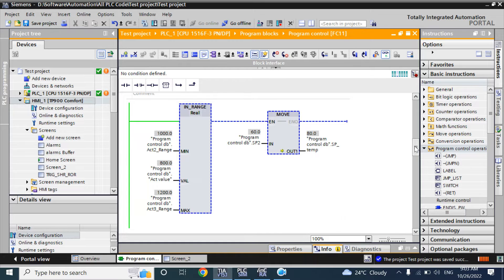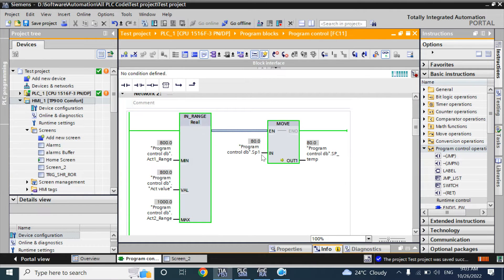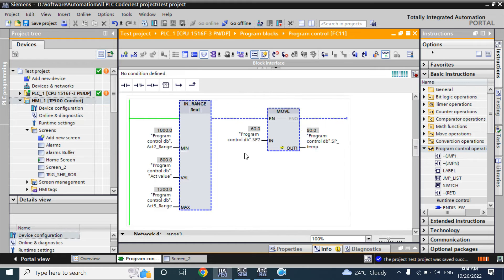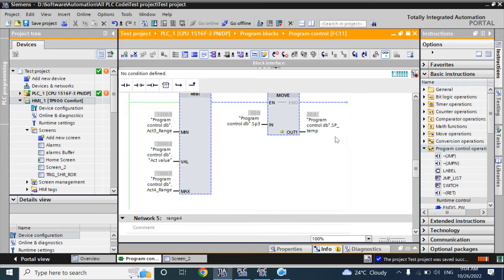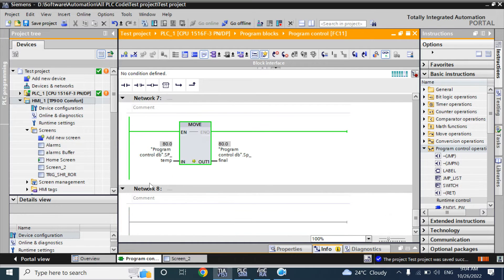When the output is high, the Move block will be enabled and whatever input is in the Move block, it will pass to that memory. Currently the value is 800, so it is passing SP1 setpoint to SP Temporary. You can see that value is 800, which is in the range between 1000 and 1200 — wait, it is not in that range, so SP2 value is not passed to that signal. We have always set the SP Temporary value and finally passed SP Temporary to SP Final, which is the setpoint sent to the motor.